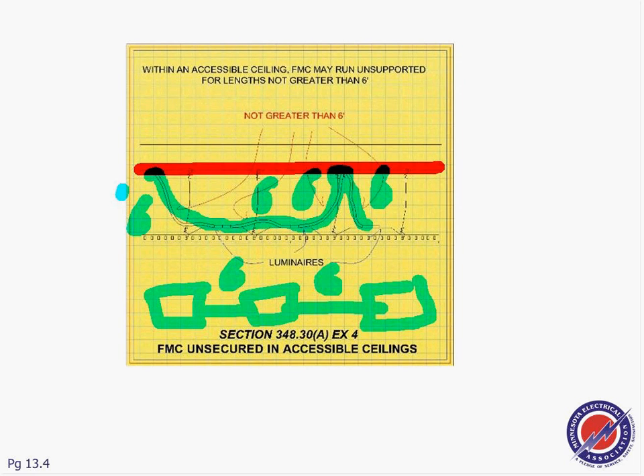So fixtures, support of fixtures, length 6 feet from the last fixture for tap connection to the luminaire. Okay, length not exceeding 6 feet from the last point of support, for an accessible ceiling or equipment in an accessible ceiling. The same thing applies, guys, if you have another machine, also for another machine in the suspended ceiling, up to 6 feet. Up to 6 feet, where flexibility is necessary after installation, length shall not exceed the following.